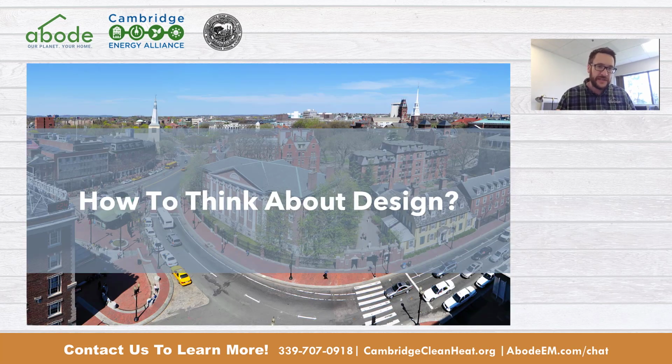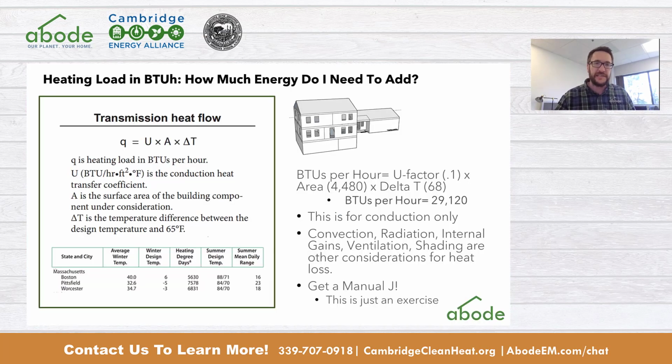So how do I think about design? I've talked a lot already about a poorly designed system and a well-designed system, but this is how I think about design. We have that same home. Take the overall R value, or U factor, which is just the inverse, times the outdoor area. Then you multiply that by the difference of temperature between what you want the thermostat set to, 70 degrees, and the outdoor design temperature, which in Cambridge is about 12 degrees. You multiply those things together and it gives you a number. In this case, it's about 30,000 BTUs. This is how old timers used to do it.